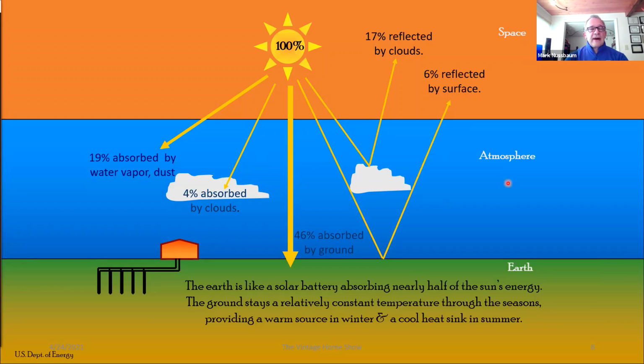So how the system works is the ground has a stable earth temperature. Here in the Chicago area, the deep earth average temperature is about 52 degrees, and almost 50% of the sun's energy is absorbed by the ground, which helps in keeping the ground at a stable temperature. That's a great contrast to the air environment, which is changing from maybe negative 10 or 0 in the wintertime up to the 80s and 90s in the summertime. The ground starts at 52 and then just moves one way or the other as we put energy in or take energy out.